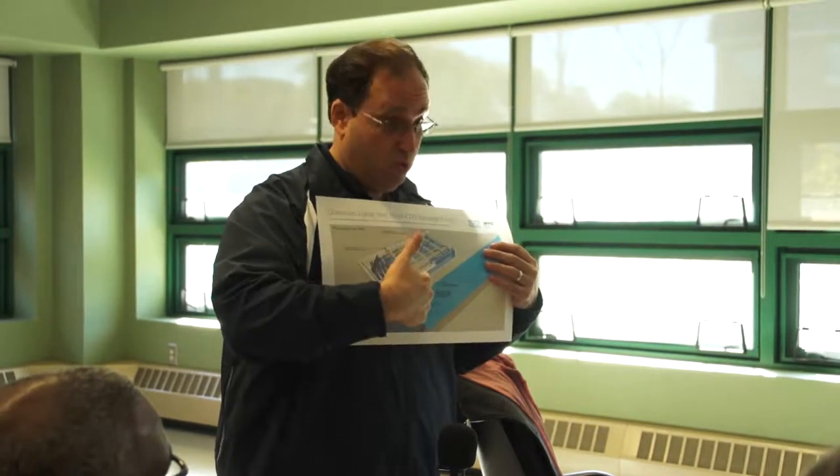There's enough storm flow getting into the collection system, it'll fill a third and fourth and so on. We like that better because if you do have some minimal storms, maybe only one or two cells will fill, and we think we get much better grit removal because the flow goes into there. It has time to better settle out. I just think it makes it easier to then remove grit later on. Operationally, I think it's simpler.